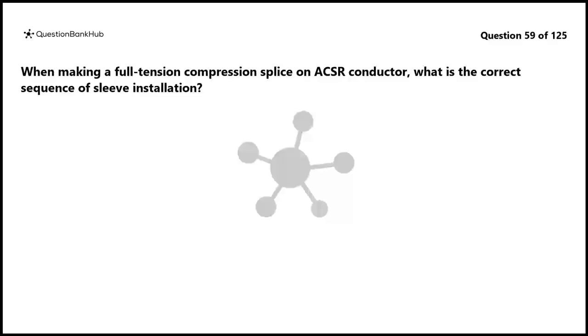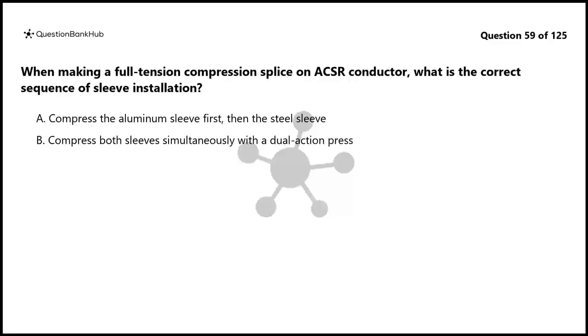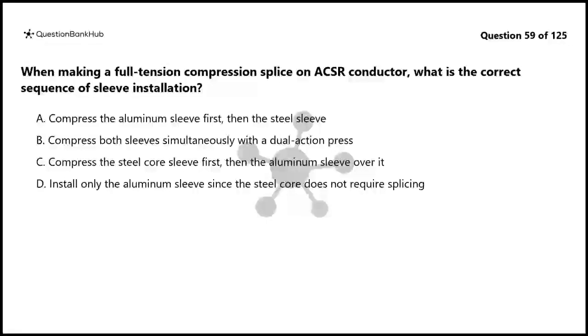Question 59. When making a full tension compression splice on ACSR conductor, what is the correct sequence of sleeve installation? A. Compress the aluminum sleeve first, then the steel sleeve. B. Compress both sleeves simultaneously with a dual-action press. C. Compress the steel core sleeve first, then the aluminum sleeve over it. D. Install only the aluminum sleeve since the steel core does not require splicing.